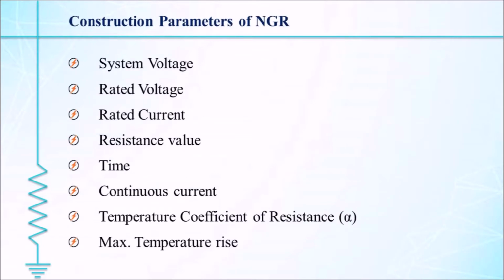Now I will explain the construction parameters of NGR. There are various construction parameters which we have to consider while designing the NGR. First is rated voltage and current of the transformer, then maximum temperature rise on occurrence of fault, temperature coefficient of resistance, value of electrical resistance, which is the most important aspect of designing, continuous current flowing through the device, and last one is rated time to pass the fault current and clear the fault.